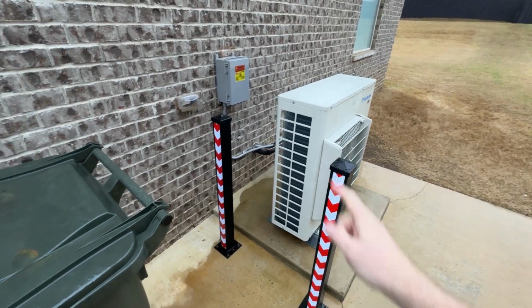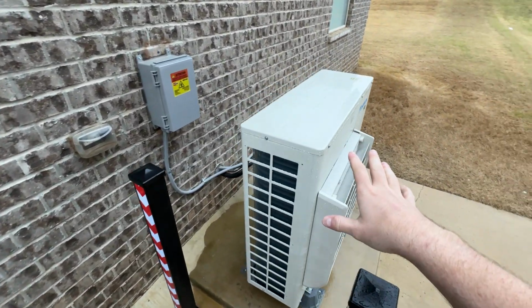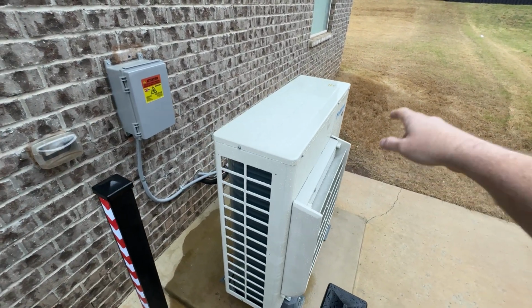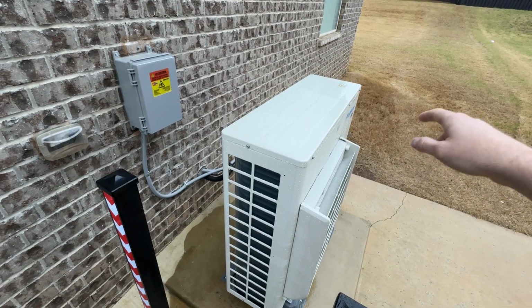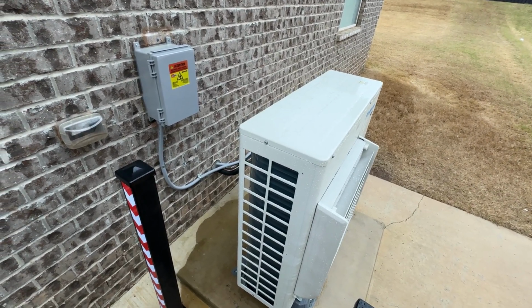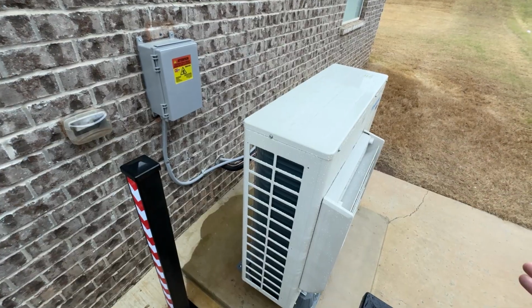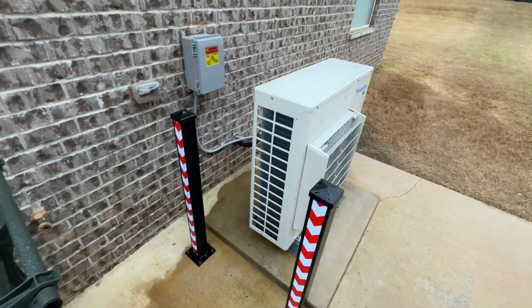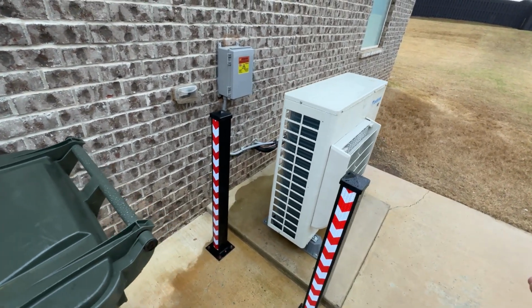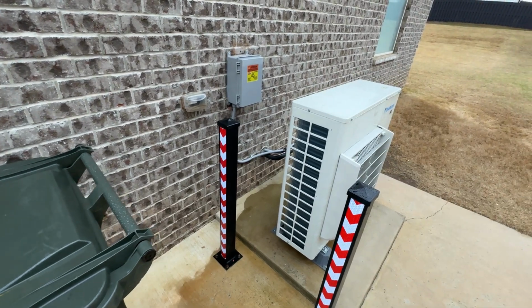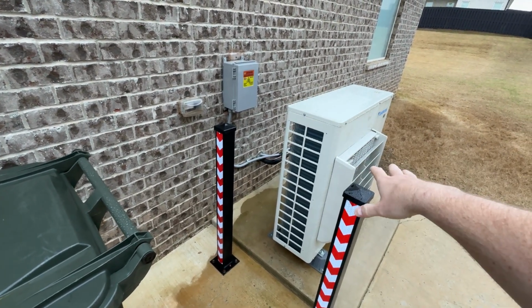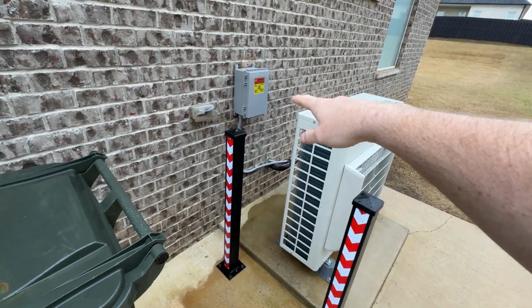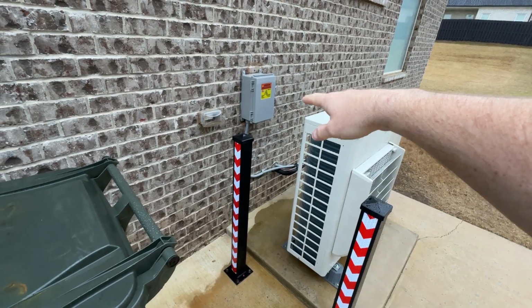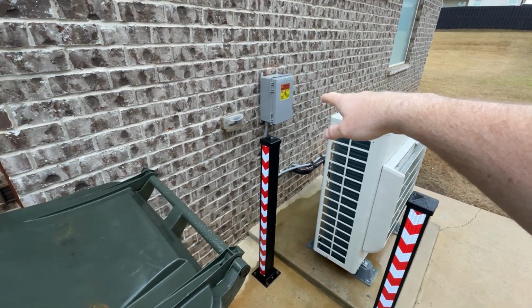And if you didn't have this box, this is what would happen. If that board fried, Daikin would come and they would probably not want to honor the warranty, because it's a $6,000 board. And they would say, well, you don't have a surge protector on this, right? Well, I do. And they only require a basic surge protector on these units. They don't require this fancy VRM that Conditioned Air does. They go above and beyond by putting that in so you can actually read it.